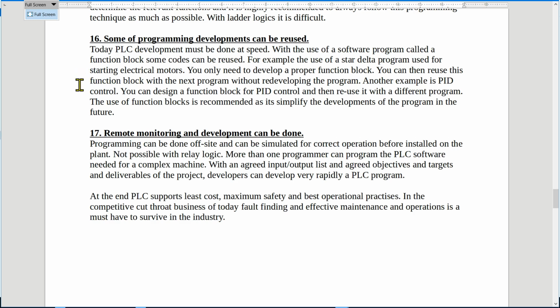And it's a very, very important, powerful tool that you must be able to use, because the function block is actually a summary of a lot of programming inside the block. It gives you a top-level approach where you can see that these are the inputs and those are the outputs, and if I get those inputs, then the output will be there. Now you can design, for example, a function block for a PID. We will discuss PID at a later stage, and we can reuse it. If I need another PID programming to be done in another program, I can just call the PID function block, insert it in my program, and give it the relevant inputs and outputs as needed. Now, the use of function blocks is recommended as it simplifies the development of programs in the future.